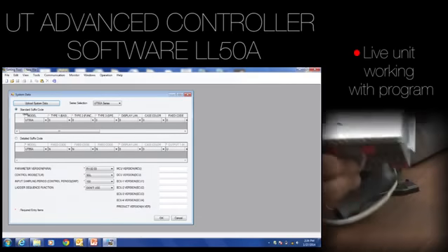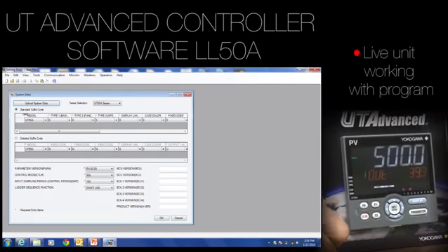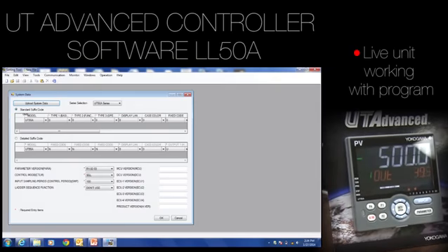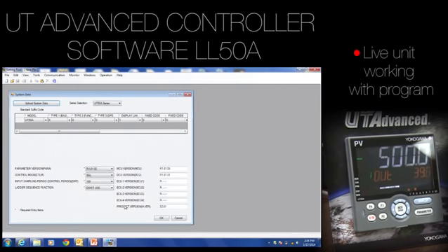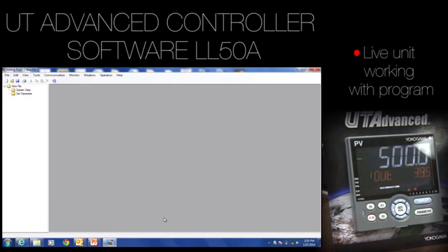And that's fine. If you have this, go ahead and configure the instrument using that. But I find it much easier to upload the system data. That way, this is going to tell the software exactly what it is. So I'm online now. I've got all the information here. So let's go ahead and upload system data. And now the software has configured itself for the controller that I'm using. I'm going to hit OK. And now I'm ready to go.